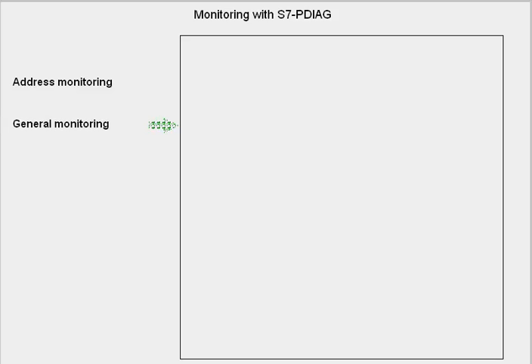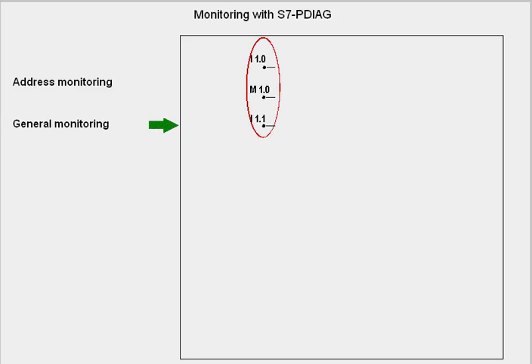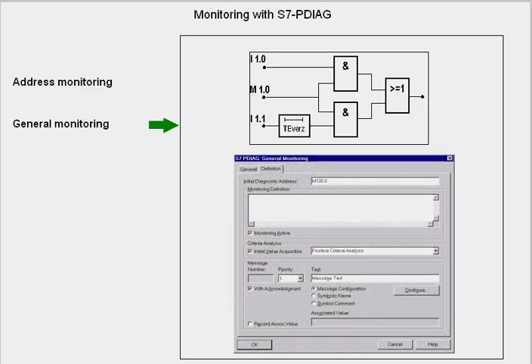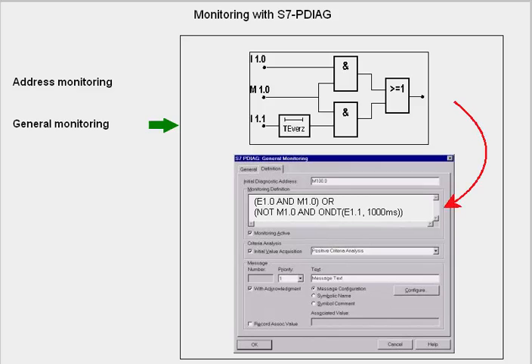For general monitoring, you can monitor any signals via a freely definable monitoring logic. In other words, this logic is not part of the user program unlike the previous case. Only if the logic of the individual operation is fulfilled will the fault message be triggered. You can design an individual monitoring logic and formulate it with S7-PDIAG specific language elements in the parameterization dialog along with the message text.